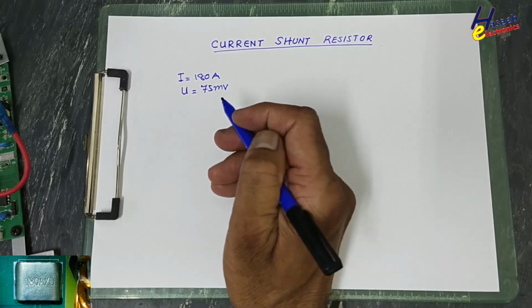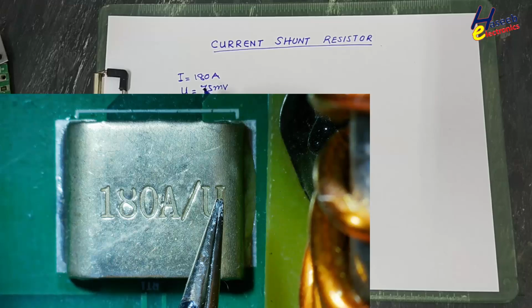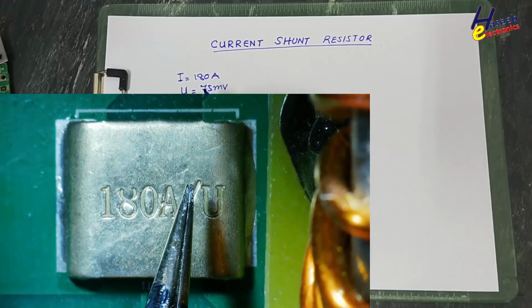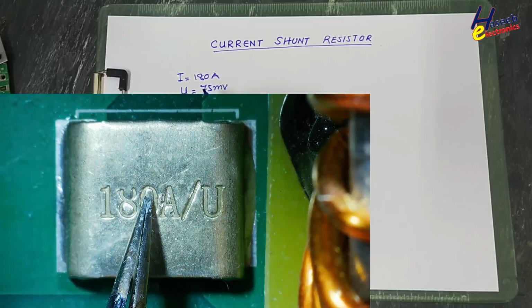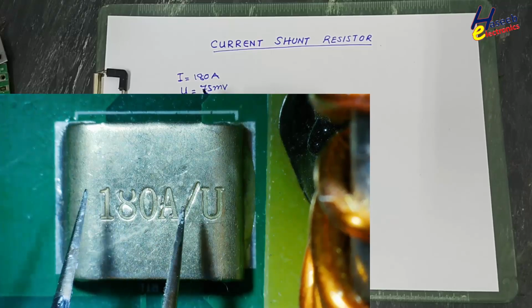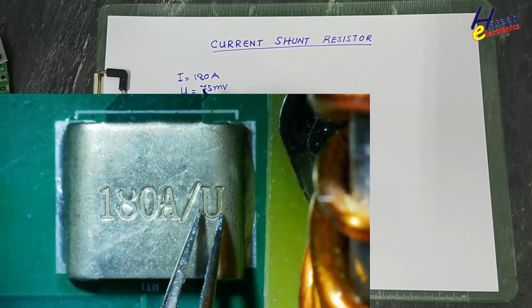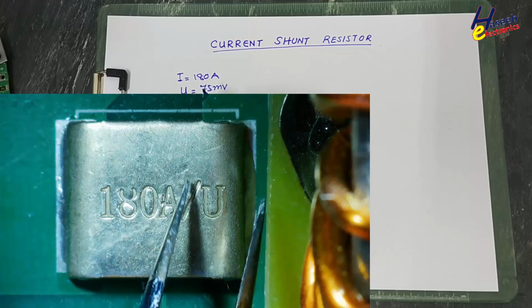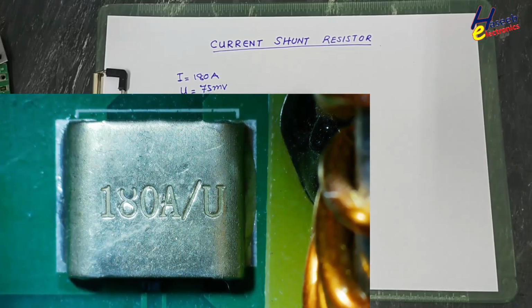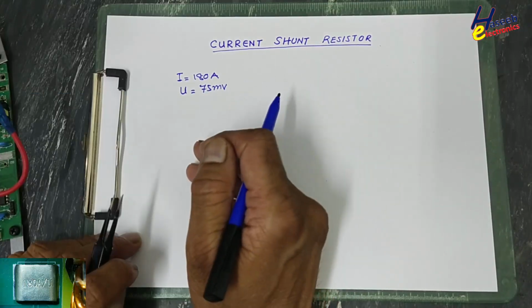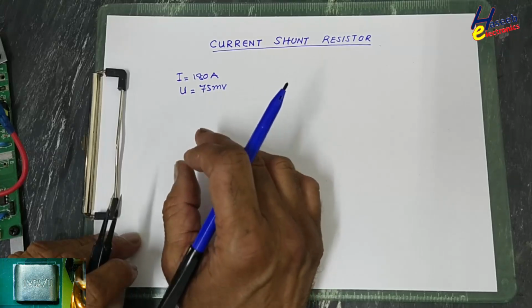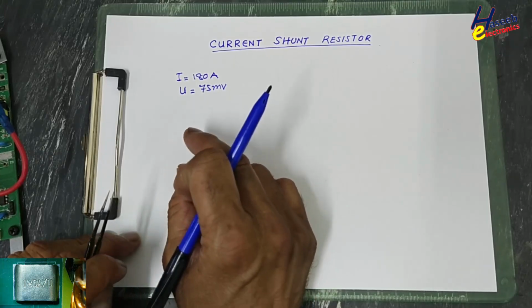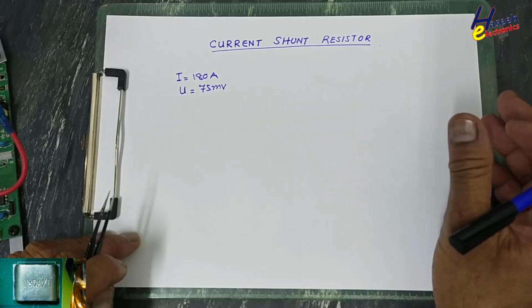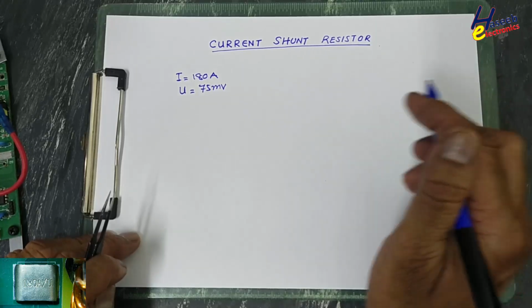That means when 180 ampere flows in this shunt resistance, that is the full scale current, it will provide 75 millivolt. This is the top limit. The current flows and the voltage drop across that resistor will be taken out for some other measurements.